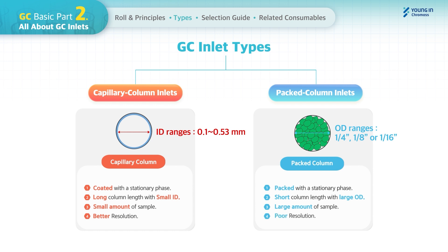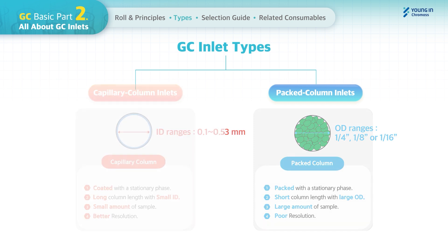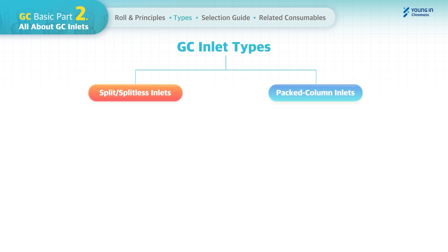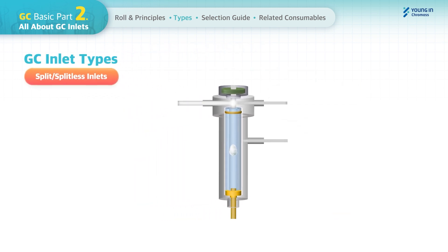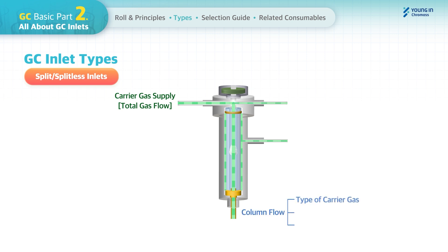The most commonly used inlet for capillary columns is the split/splitless inlet. Let's look at the schematic gas flow by inlet type. In the split/splitless inlet, total carrier gas flows into the inlet, passing through the septum purge line and the inlet liner. In the liner, the set column flow goes into the column while the rest is vented out through the split vent line.